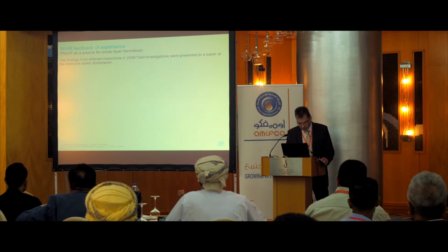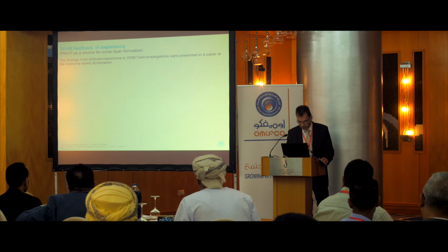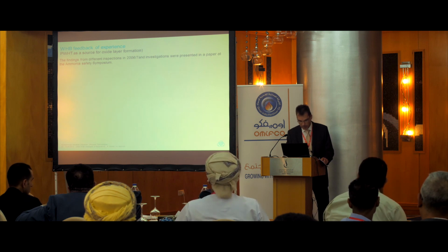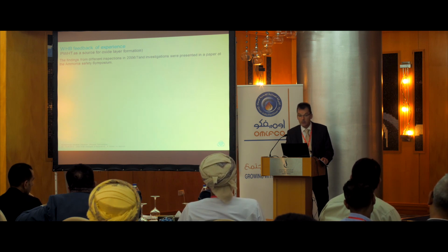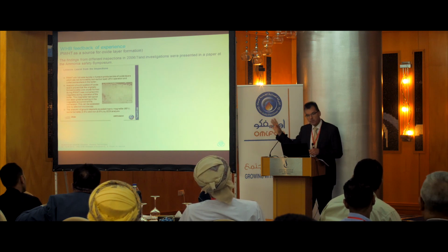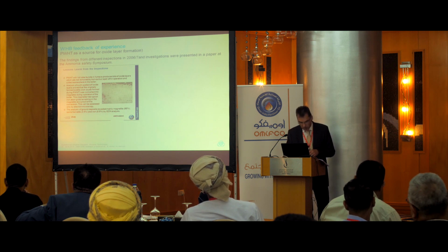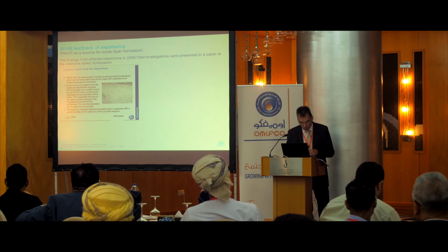From the material samples of spalled-off oxide layers, a clear origin from the post-weld heat treatment could be proven by electron scanning microscopy. Here's just a short description. I will not read it down. What you find when you do the electron scanning microscopy. But the forming of magnetite is shown on the slide on the left side. You see how it looks like normally here on the left side. As it was not really possible to flush out completely spalled-off oxide layers or remove them during initial boil-out, the logical solution was to prevent its formation during post-weld heat treatment.